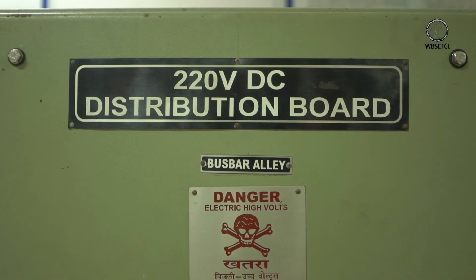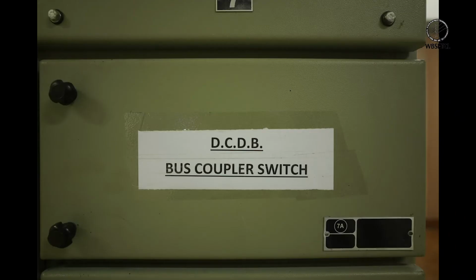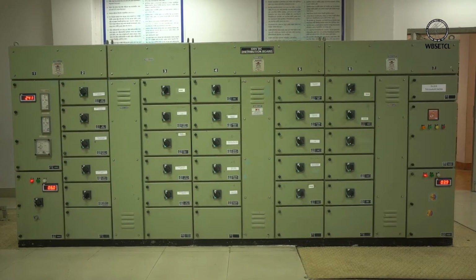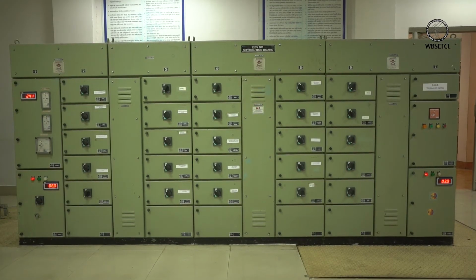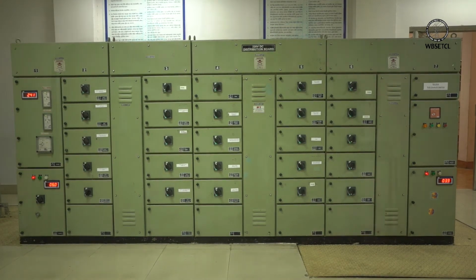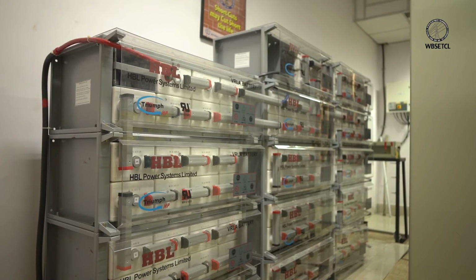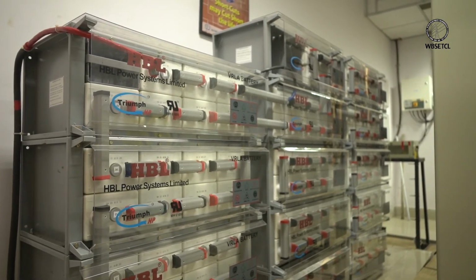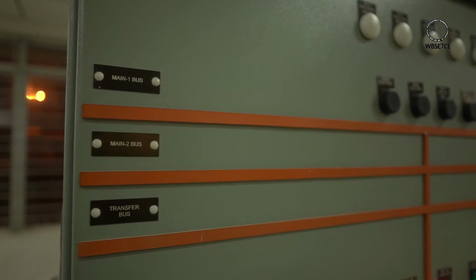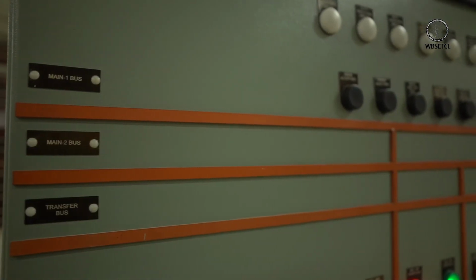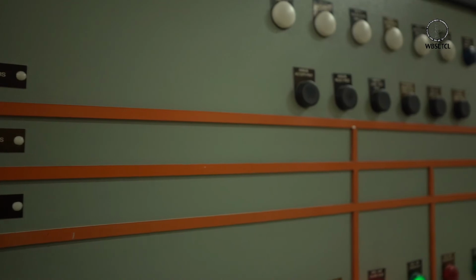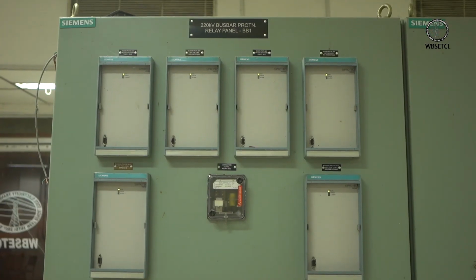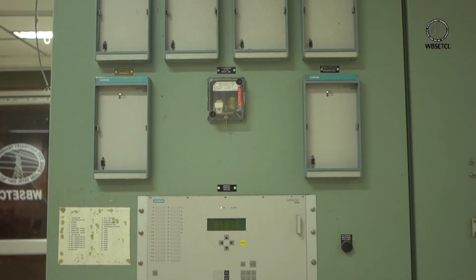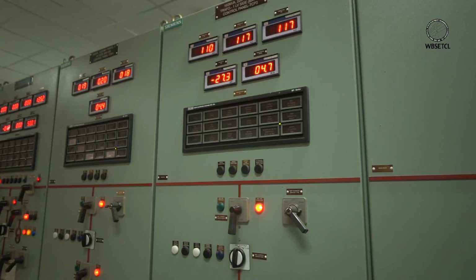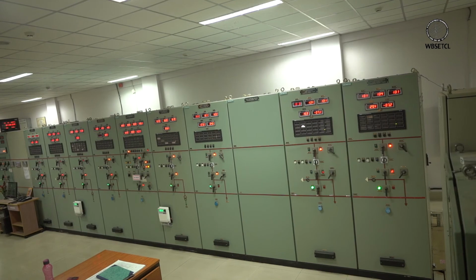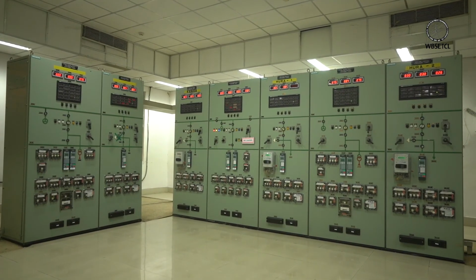The DC distribution system with two bus sections and a bus coupler arrangement is backed by two numbers of separate 220 volt DC banks, including one newly installed VRLA battery set, providing more flexibility to system control and protection as well. The Hura 220 kV substation has inbuilt features like double main, one transfer bus system or DMT, bus zone protection in 220 kV class along with bus bar protection system, one main and transfer bus system in 132 kV and 33 kV class respectively.